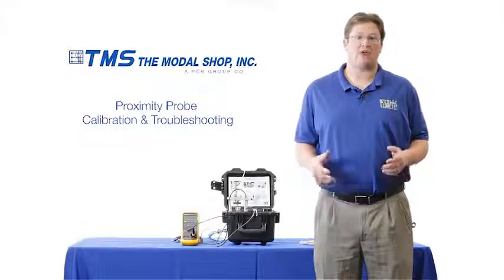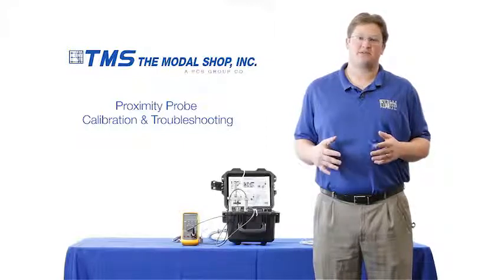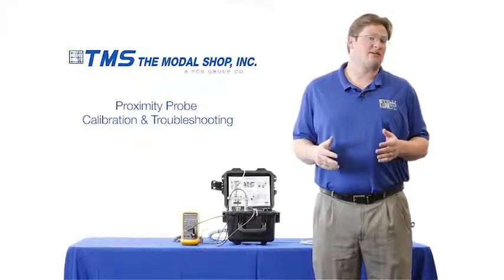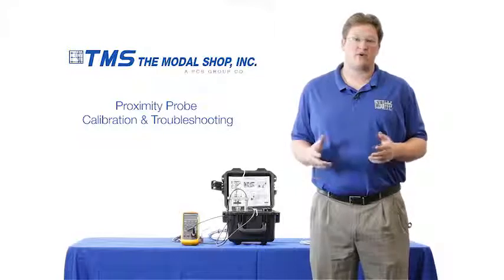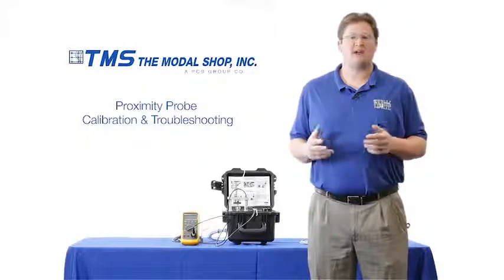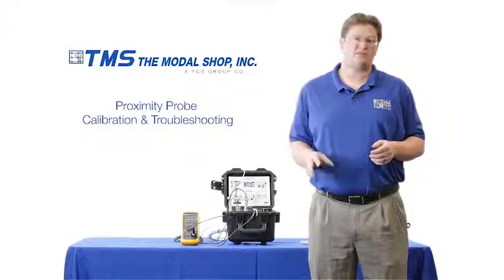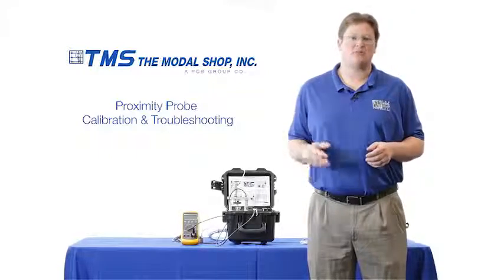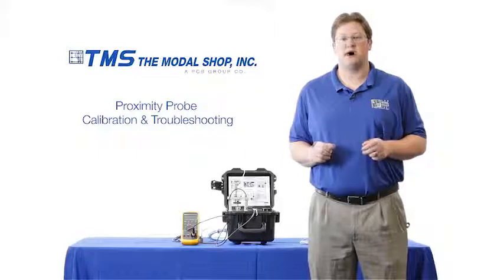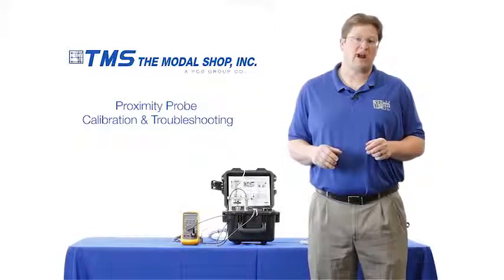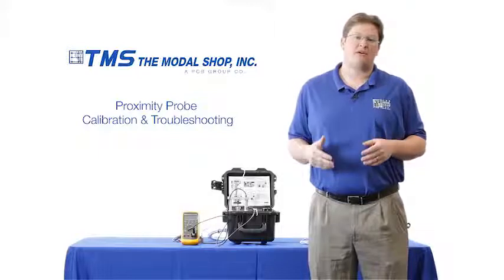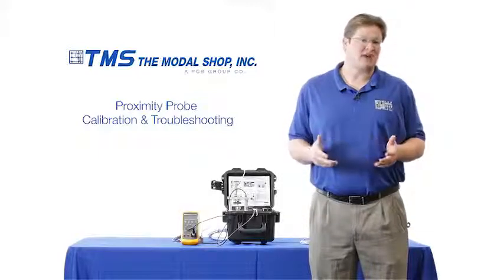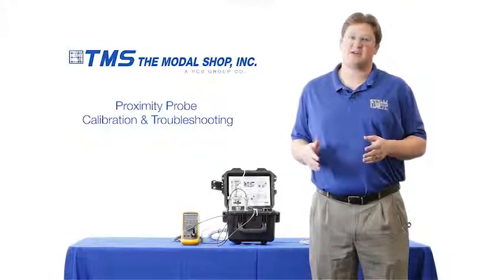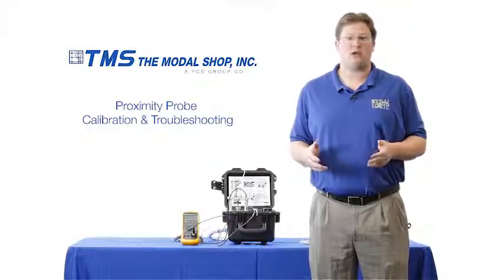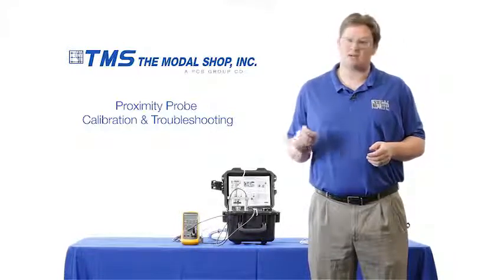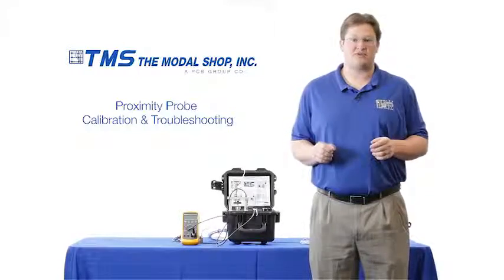Proximity probes, or eddy current probes, are used to protect some of the world's most critical equipment like gas and steam turbines from vibration issues. These systems rely upon precise cable lengths, and so does the machinery protection system. The machinery protection system is relying upon a 200 millivolt per mil or 7.87 millivolt per micron output from the proximity probe. Mismatched cabling or incorrect cable lengths can significantly throw this dynamic output, which causes false trips, false alarms, or late alarms and catastrophic failure.